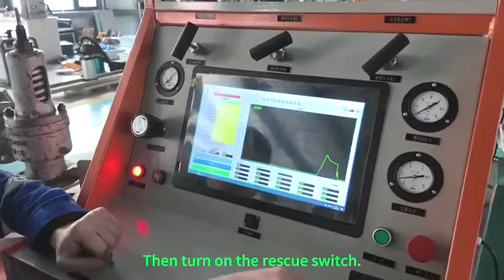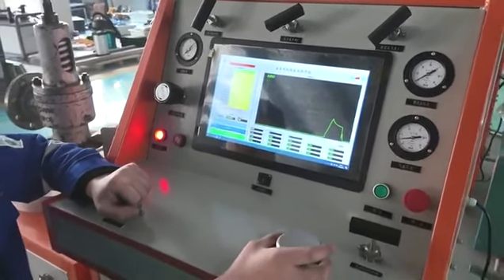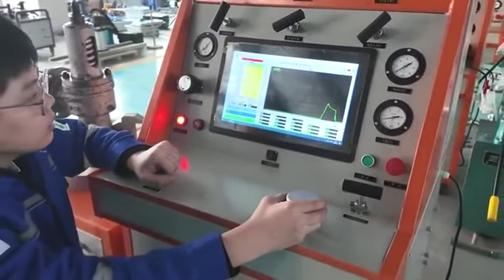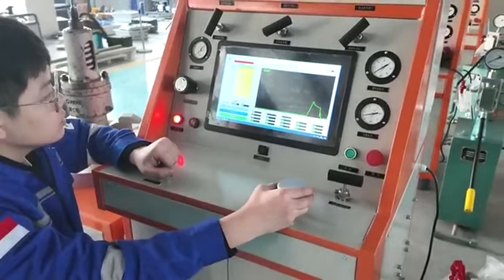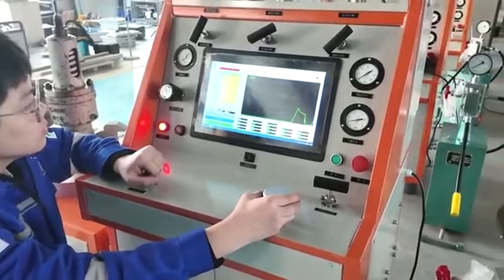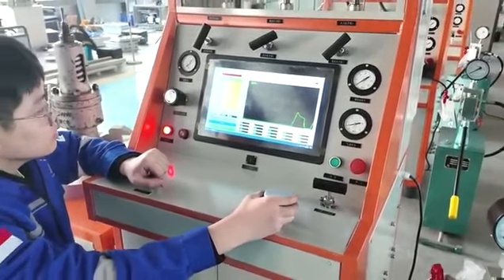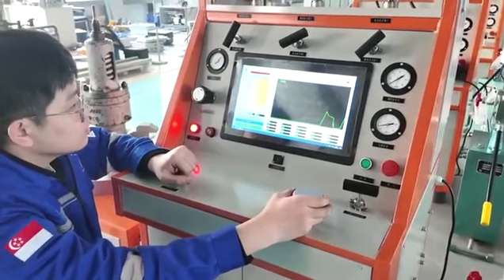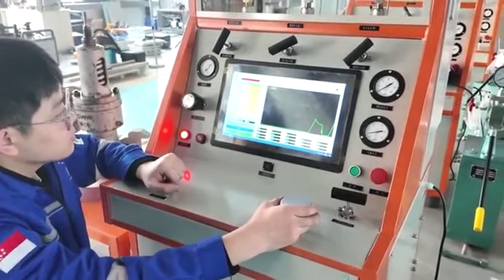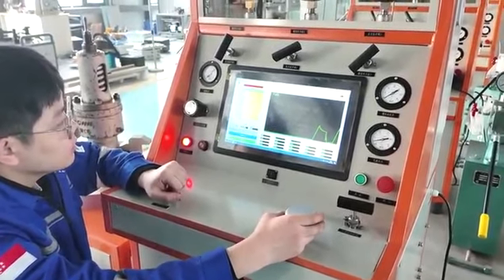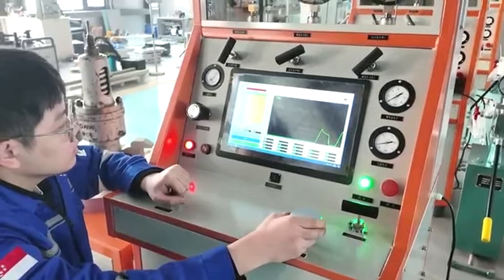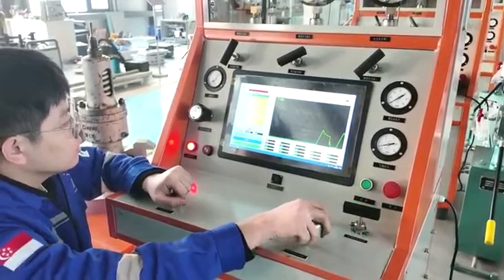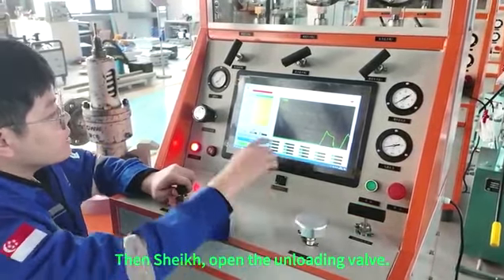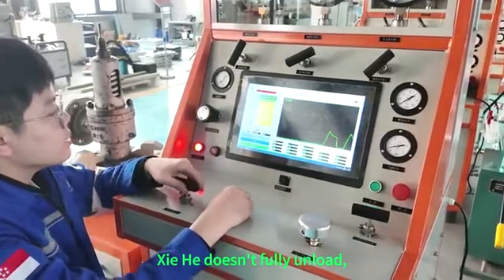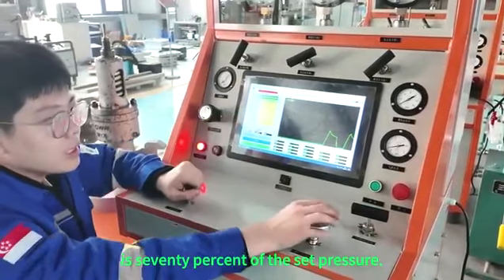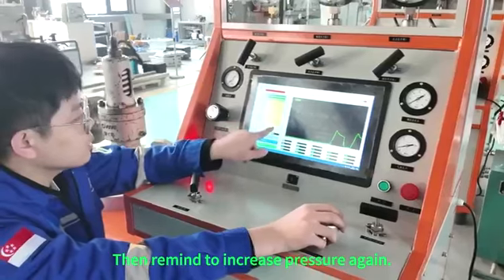Operation steps: then turn on the switch. Then open the unloading valve. See, it doesn't fully unload; it unloads to 70% of the set pressure. Then it reminds us to increase the pressure again.